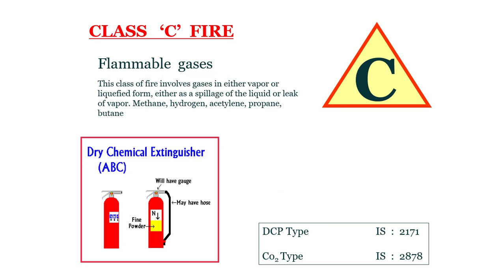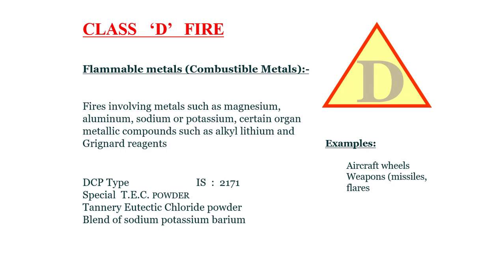Class C fire — flammable gases: this class involves gases in either vapor or liquefied form, such as methane, hydrogen, acetylene, propane, and butane. DCP type IS 2171 and CO2 type IS 2878 are recommended to extinguish this fire. Class D fire — flammable metals: combustible metals such as magnesium, aluminium, sodium, potassium, and certain organometallic components such as alkyl-lithium and Grignard reagents. Examples include aircraft wheels. DCP type IS 2171 and special DCP powder are used.